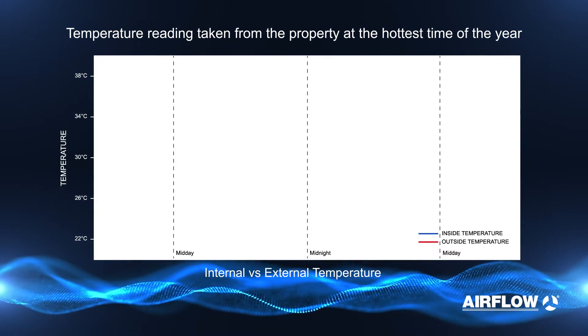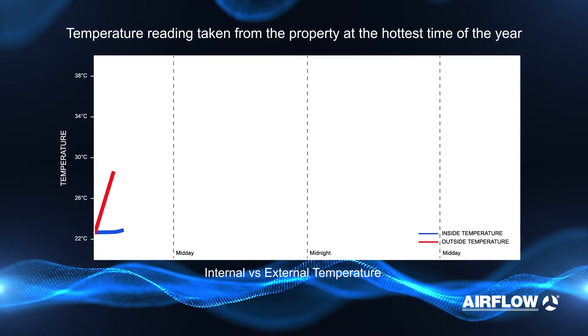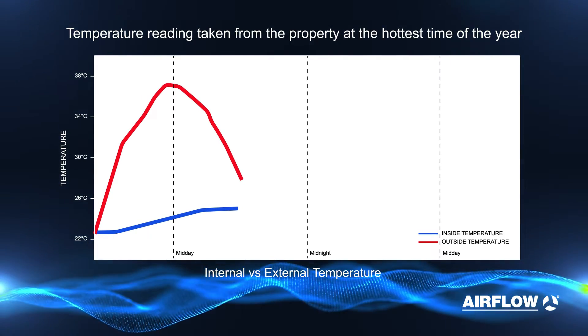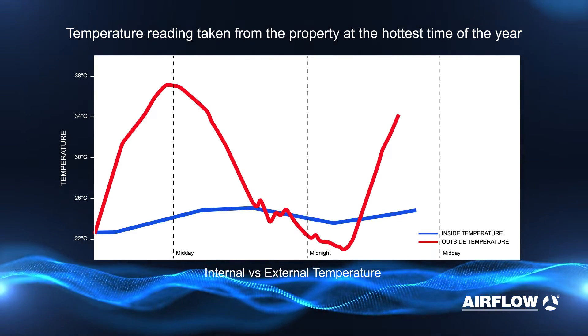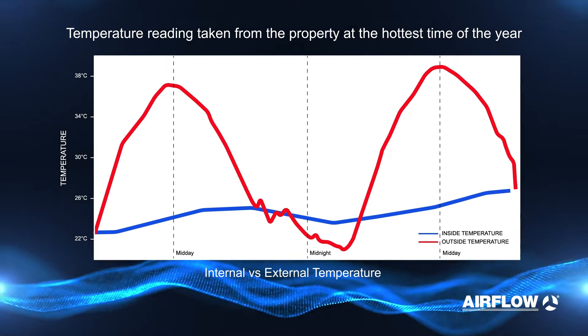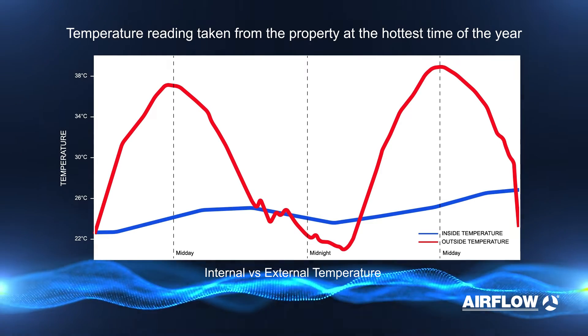From this graph you can see the external temperature is at 39.7°C, the average internal temperature is at 25.4°C, and we're delivering air — at the point where the air is hottest from outside — at nearly 9°C. This shows how this system can maintain a pleasant internal temperature irrespective of the heat externally.